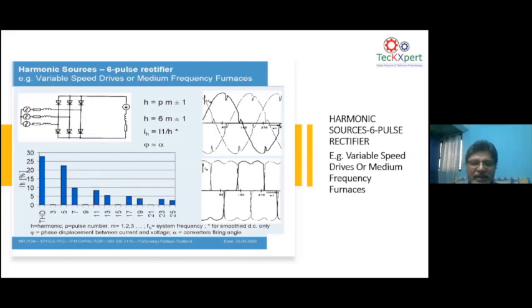But an active front-end drive may not produce this 3, 5, 7 and all that. What it generally produces is a lot of higher order harmonics. Because if you go for an active front-end drive, none of these harmonics will be there, so everybody will be happy: oh, the active front-end drives, I'm very happy, not producing any harmonics. But an active front-end drive produces higher order harmonics.